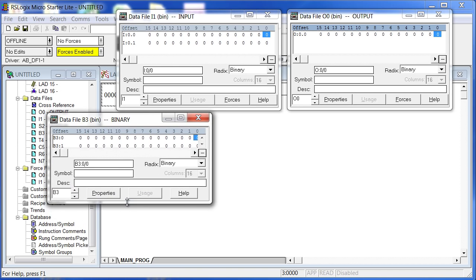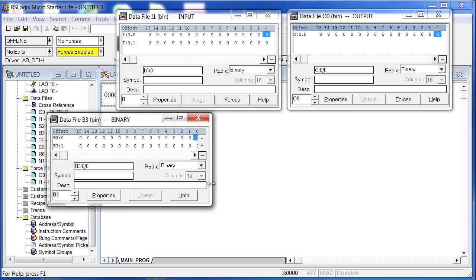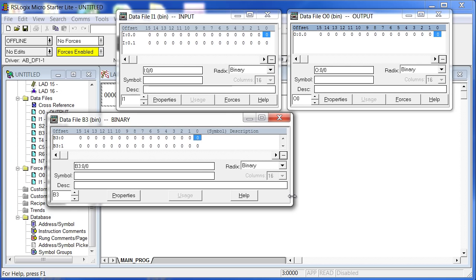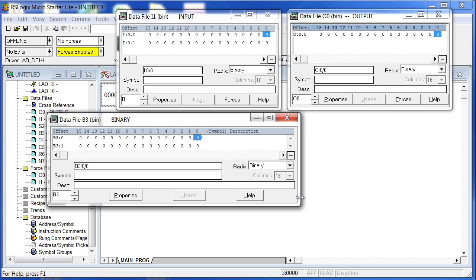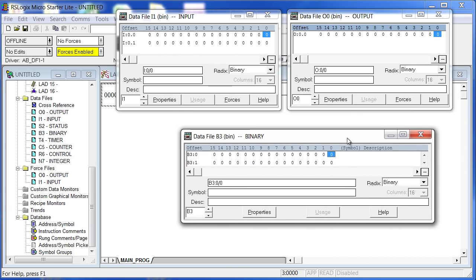I'll also double-click on B3, lock it on top, and drag it up — we don't need all 32 sixteen-bit words, so we'll just leave two showing. I'll stretch it out so you can see the symbol and description fields. The symbol is a unique identifier that points to B3:0/0, which is actually a pointer to a memory location. For all intents and purposes, think of B3:0/0 as a physical memory location.